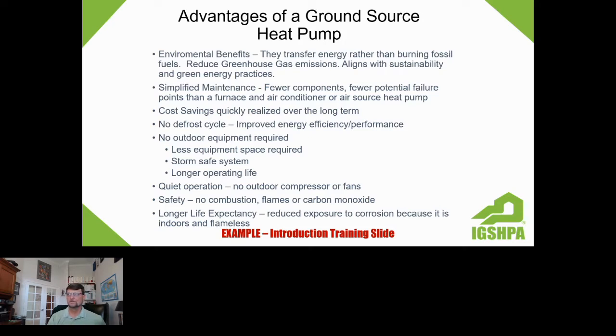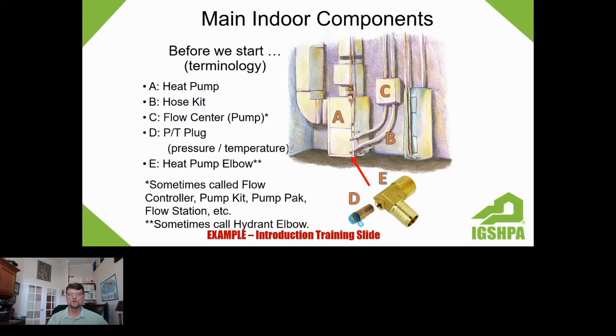We also show some basic overviews of the main components that are in the building that really compose the geothermal heat pump system, like the heat pump itself, hose kits, flow center pump systems, and some of the fittings that are involved to make connections to do service work, diagnostics, or maintenance on them. So it really is going to be beneficial to give you a preview before you get into the installation class, knowing what to expect as part of a system, as well as the earth loop connection methods.